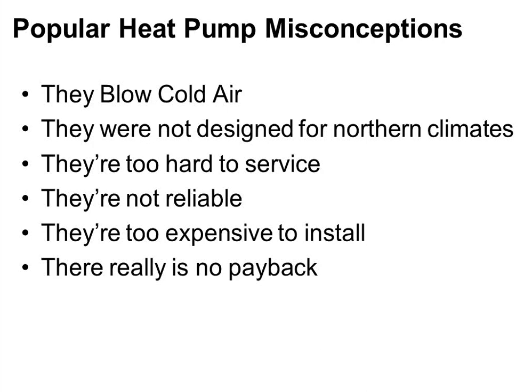The reason that people have complained about servicing those over the years is because now they have to wire up that valve. So they've got to buy a stat that can handle that. They've got to pull extra wires from the thermostat to that valve or to the control panel for that valve. And then they have to figure out, is this a normally open or a normally closed valve? Is my thermostat set up for normally open or normally closed? And then get all this stuff wired correctly and then cross their fingers and hope they did it right.